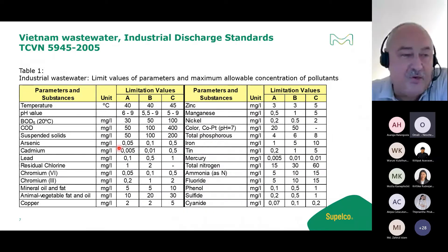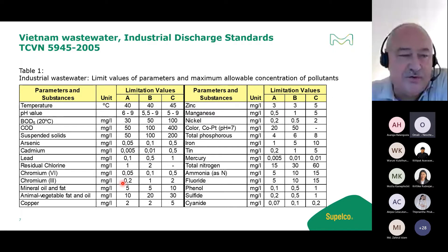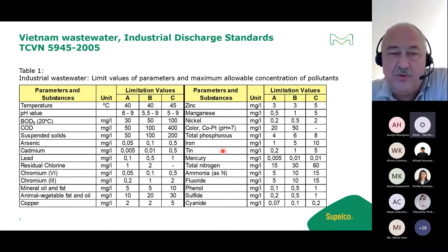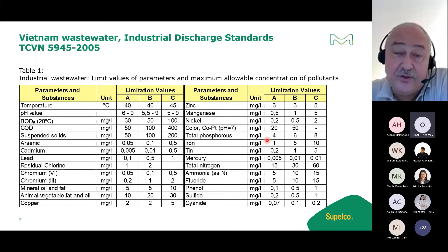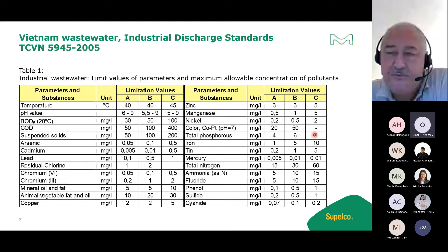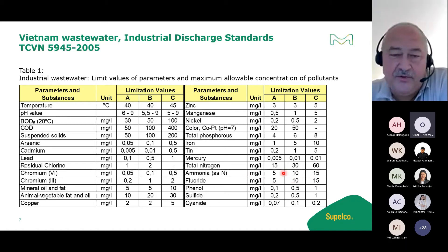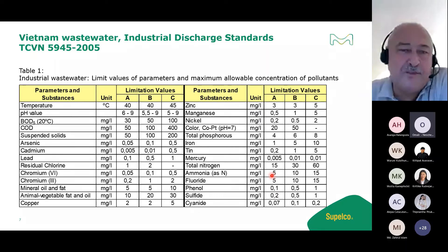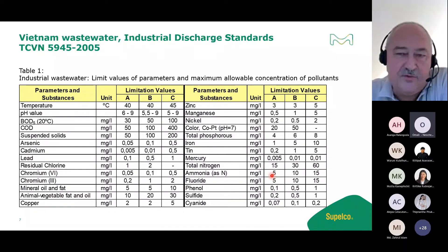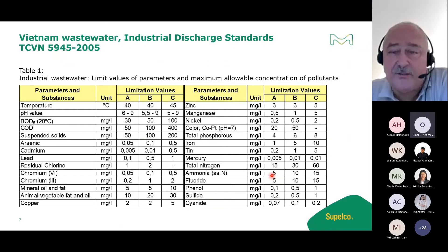The Vietnam standard also covers arsenic, cadmium, lead, residual chlorine used for disinfection, chromium 6 and chromium 3, nickel, and phosphorus - with limits of 4, 6, and 8 mg/L depending on discharge class. Total nitrogen is 15, 30, and 60 mg/L, and ammonia as nitrogen is 5, 10, and 15 mg/L. This makes sense because a treatment plant will further treat the water.